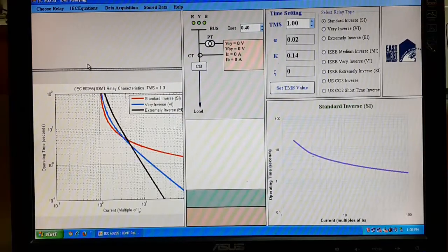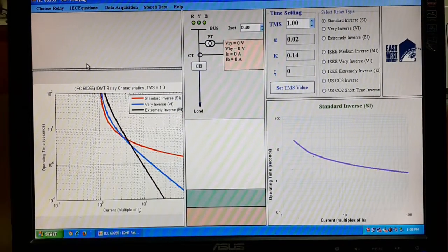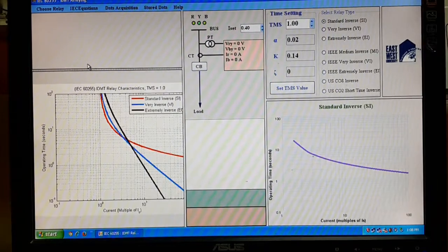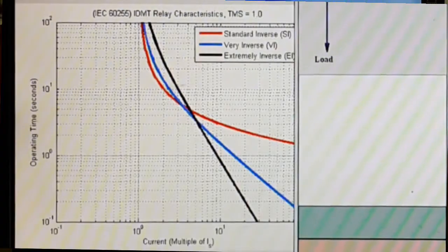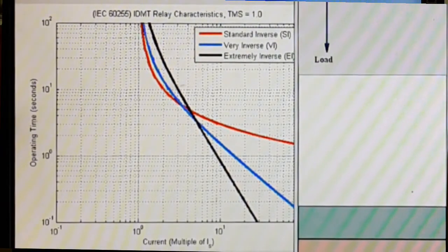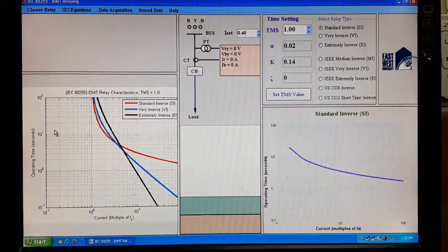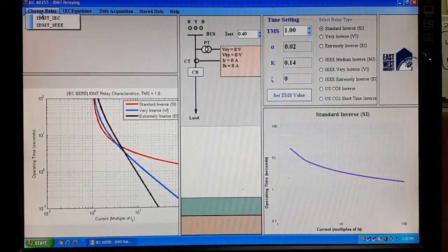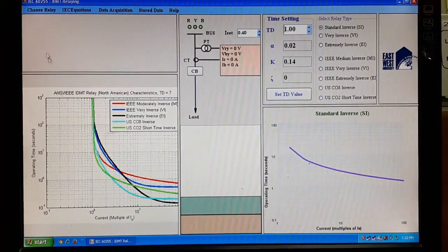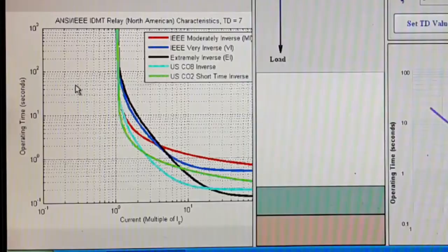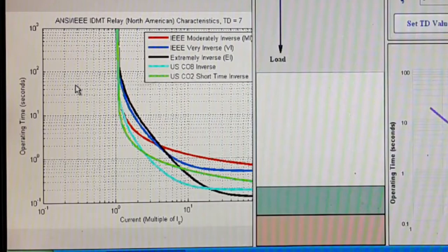For theoretical study, under IEC relays there are three characteristics: standard inverse, very inverse, and extremely inverse. Under IDMT and IEEE, the curves are: IEEE moderately inverse, IEEE very inverse, extremely inverse, US CO8 inverse, and US CO2 short time inverse curve.